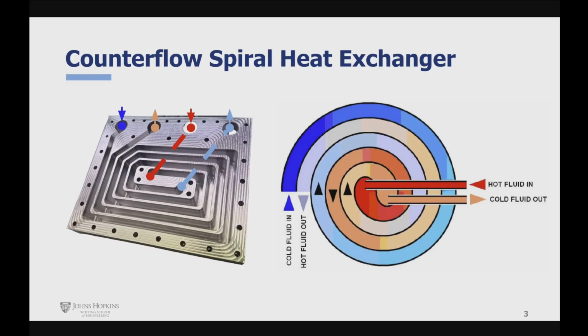Here is an internal view of the device, along with a schematic on the right side showing the basic design. Our heat exchanger is a type of spiral heat exchanger, in which heat transfer occurs between two parallel counterflowing fluid streams, which are wound together in a spiral. On the left side, you can see the machined spiral channels through which the hot and cold water flows. In our device, the hot water is first redirected to the center of the spiral and then channeled outward, exchanging heat with the cold water stream in the process. Cold water enters at the outside of the spiral and is channeled to the center, achieving counterflow.